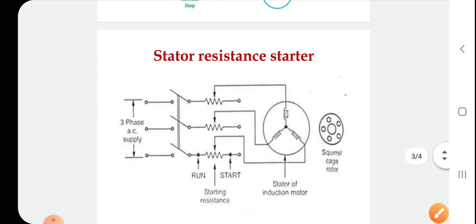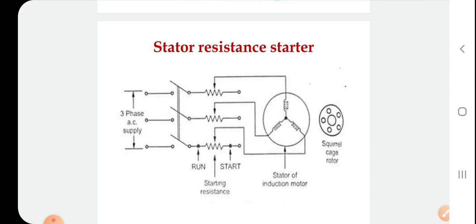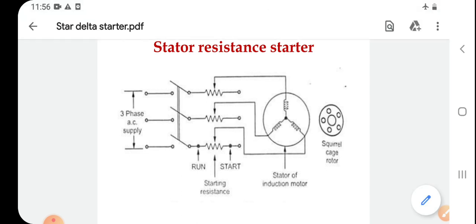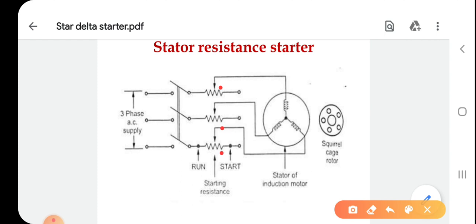Now let us discuss the stator resistance starter. This is the schematic diagram of the stator resistance starter. A reduced voltage is applied to the stator of the induction motor. Three resistances are added in series with each phase of the stator winding. Initially, the resistances are kept at maximum position in the circuit, due to which a large voltage drop occurs across the resistance.